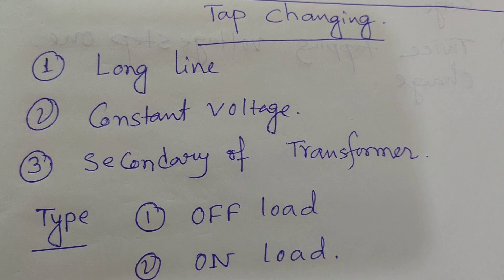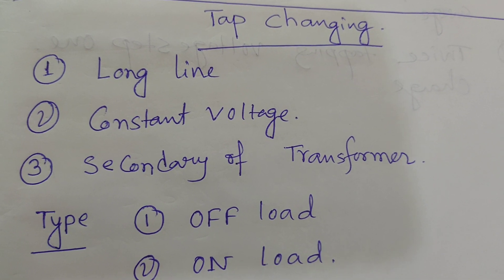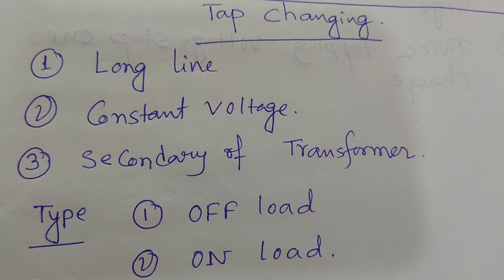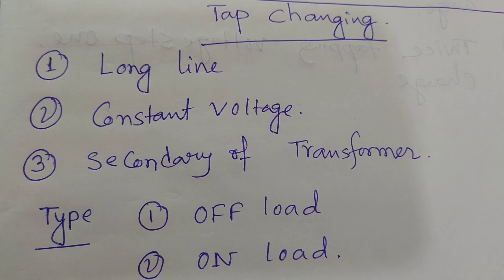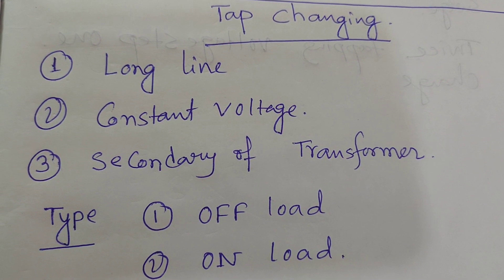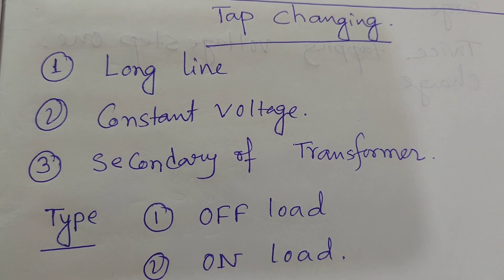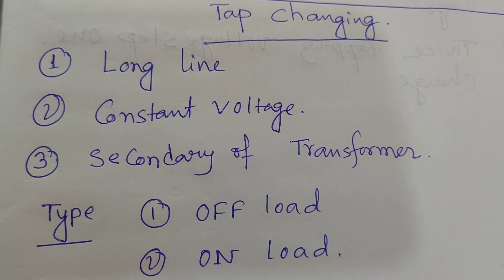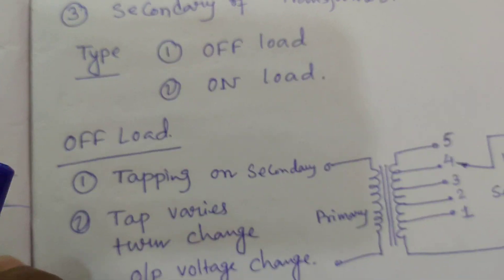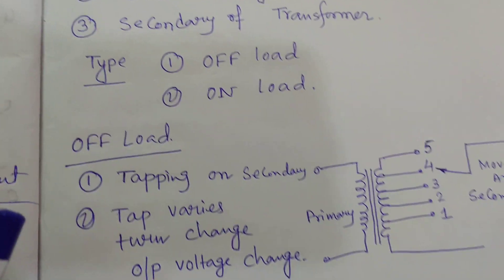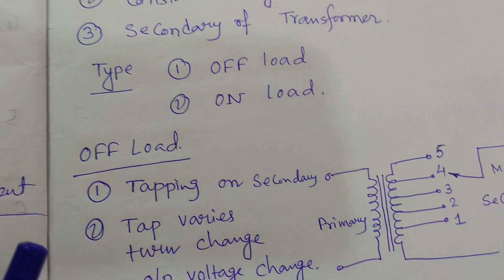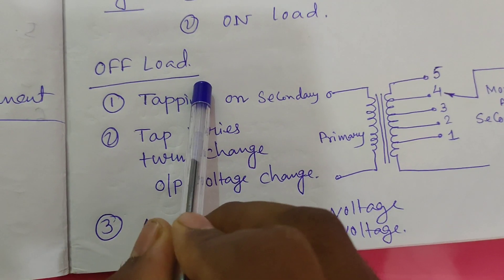We change the tap accordingly for our requirements. There are two types of tap changing methods: one is the offload tap changing method, and the other is the onload tap changing method. Offload means the load has been disconnected — the load will be disconnected when the tapping is changed. Let us discuss the offload tap changing method.